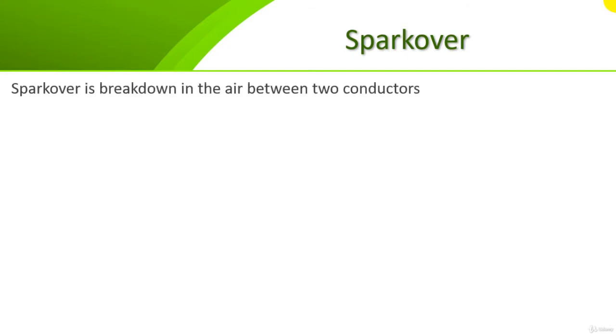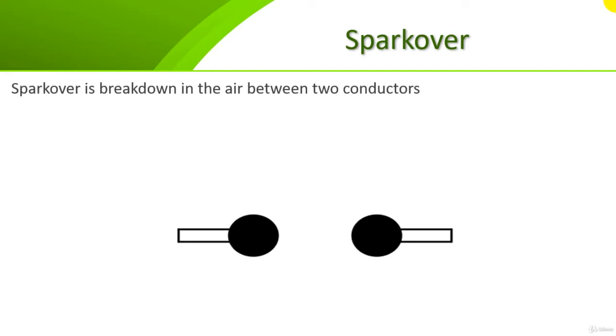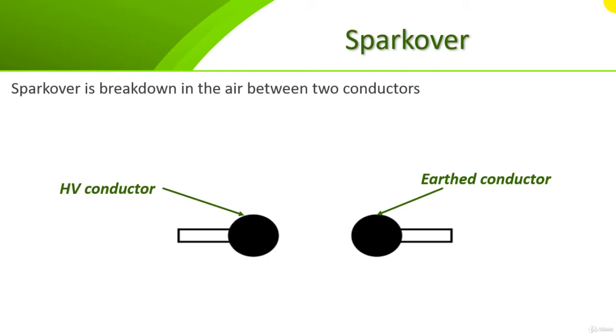Spark over is simply a breakdown in the air only, between two conductors. If we have a high voltage conductor and an earth conductor, a very high voltage difference applied between them creates a high electric field. This high electric field causes electric breakdown in the air, which appears in the form of a spark — called spark over.